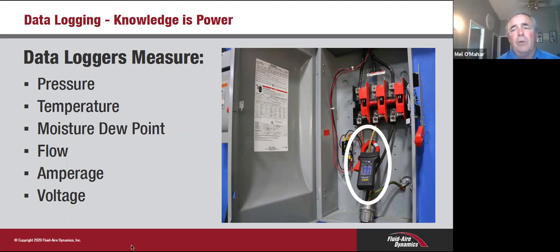But whenever we get into a new customer and we're not familiar with what kind of demand they have, we always start out data logging them, because we come in there and we can see: is the system sized properly? Are they using the right type of compressor? Are we matching it to their flow? Do they have different shifts that require different flows? So whenever we come in on a sales call, we try to data log first off, because now we know what we're dealing with.